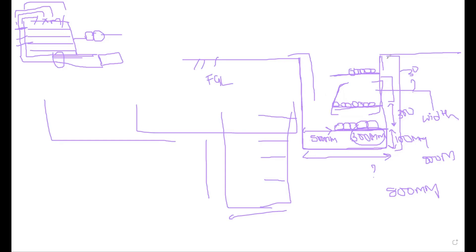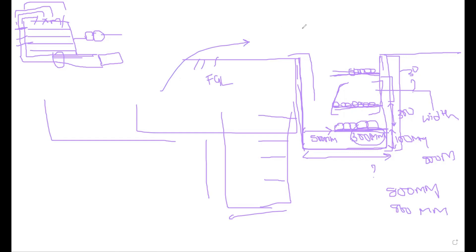This is the cable trench sizing calculation for civil foundation. The 800 x 800 mm cable trench is suitable to accommodate three types of 300 mm cable trays. The first thing you need to do is size the cable tray based on the number of cables it will carry, and after that you size the cable trench.